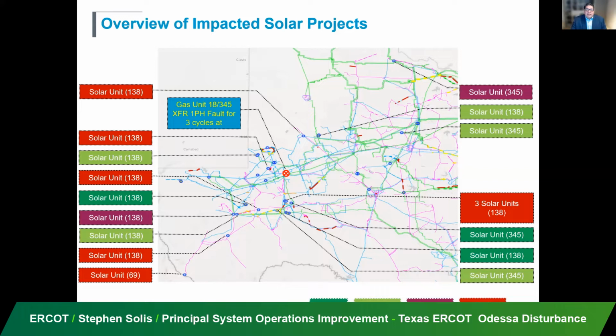We have 138 kV, 69 kV, and 345 kV as our nominal transmission backbones. And on each of those kV levels, we saw solar units trip off or temporarily reduce the megawatts. And we saw it at different time frames, meaning some responded where they dropped off megawatts, but recovered within 10 seconds. Others took a little bit longer to come back, maybe within a minute. Others between 1 and 5 minutes, and some quite farther beyond that. So when we looked at the megawatt recovery, it was not as expected.